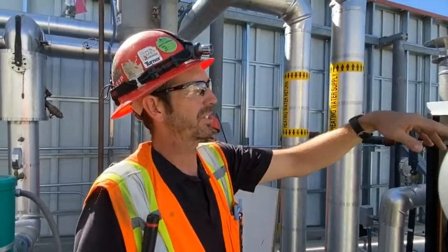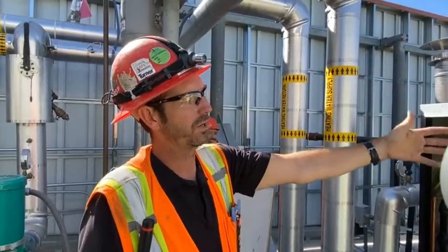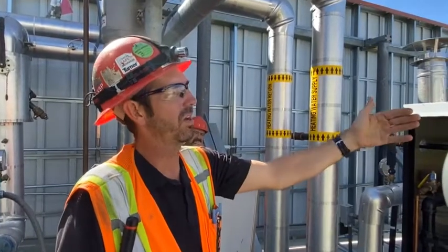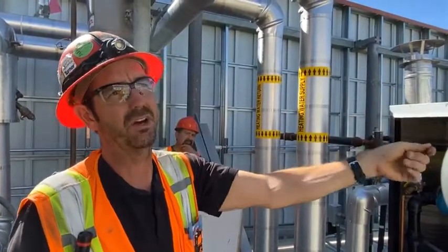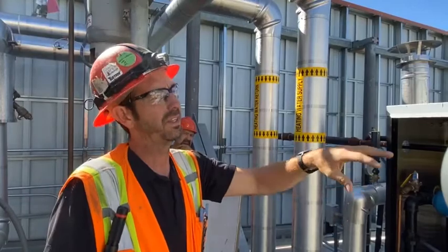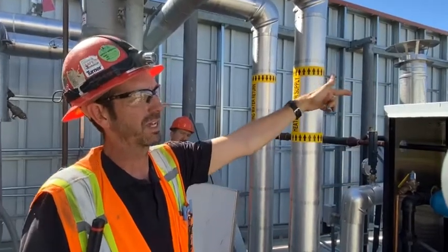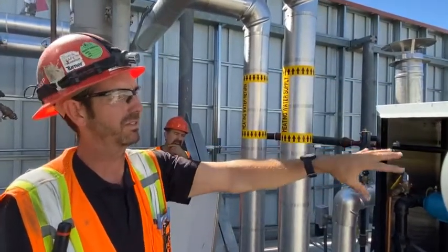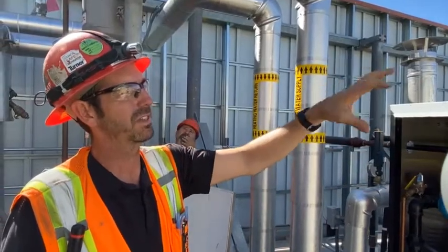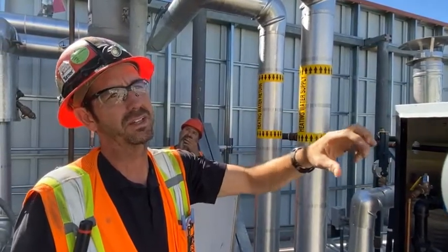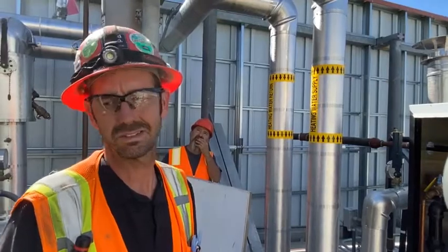Like Troy mentioned, when you're fully in command of all the switches inside at the bottom of the unit, they all need to be in remote mode. And then these are linked together, right? There's a master and then the two slaves. And the BMS, the master is this first one. The BMS guys just enable the system, and then the master will do all the staging of the other units.